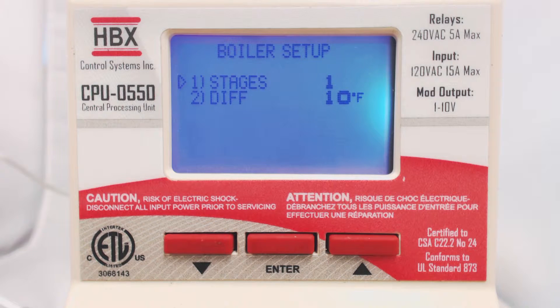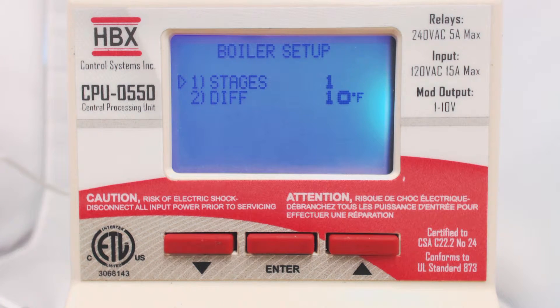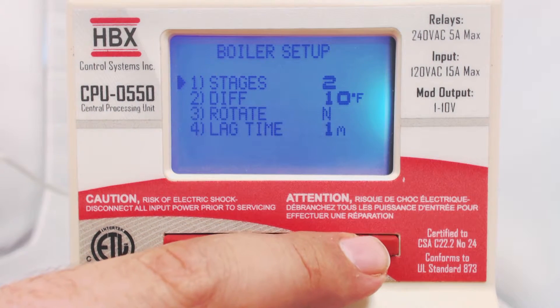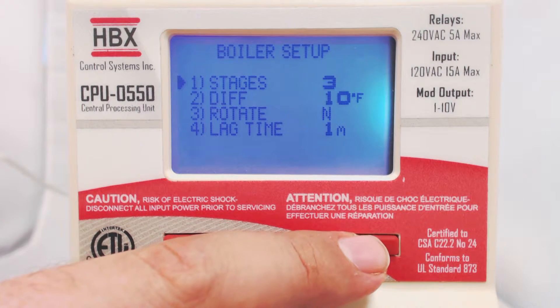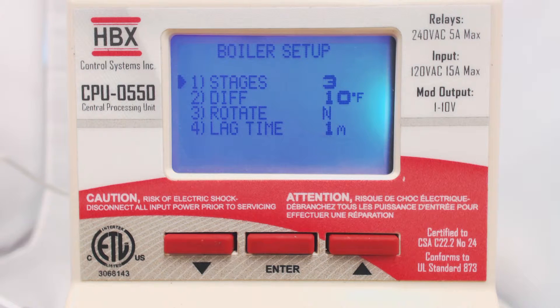Here we can change the number of stages. By default, the control comes programmed for one stage, and you can adjust the differential. To change for multiple stages, press Enter and then the up arrow button. You will notice that the screen intuitively changes with the number of stages. The control will not show any options that are not applicable to your choice.